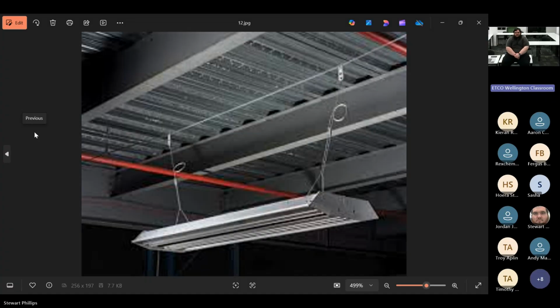So if you've got a 3-core and earth 25 mil cable, and you've got 3 of them to run, how many catenary wires are you running? So if I've got 3 25 mil 4-core and earth cables to run, how many catenary wires? One for each, yeah? Any advances on that? Three cat wires. Yeah, so I'd be going 3 cat wires minimum. Sometimes you might even double up on the catenary wires and have 2 cat wires per cable.